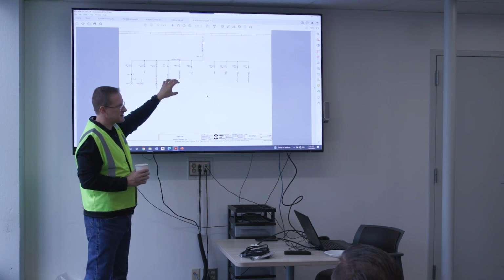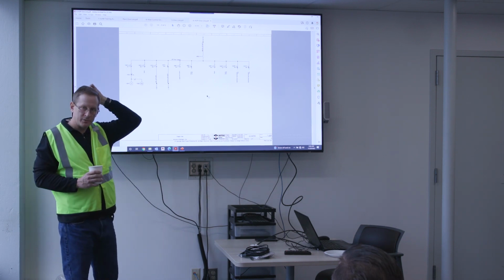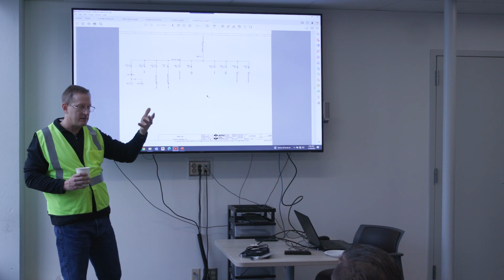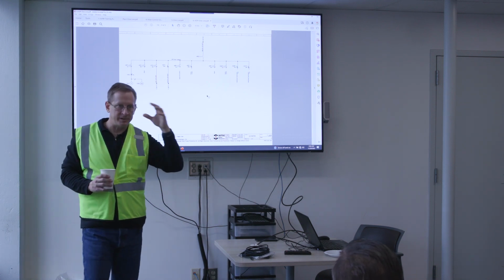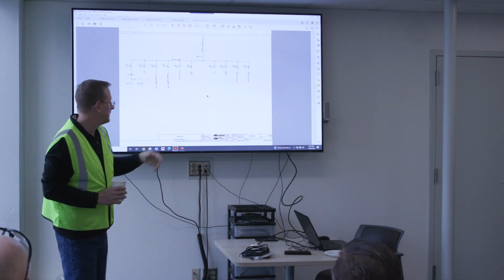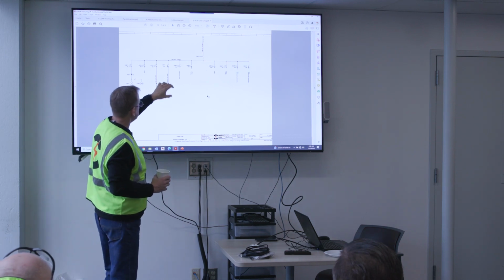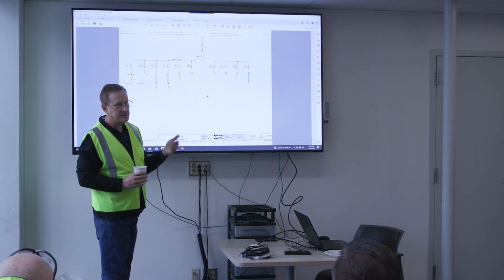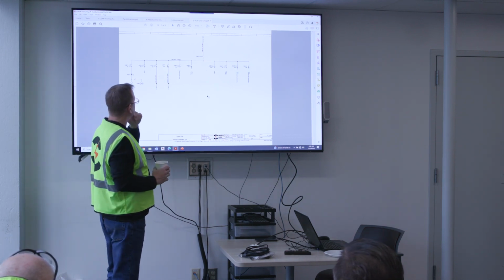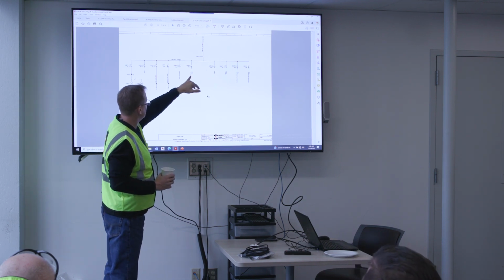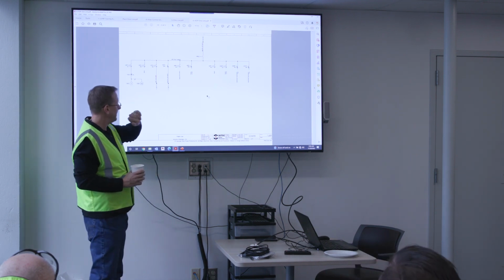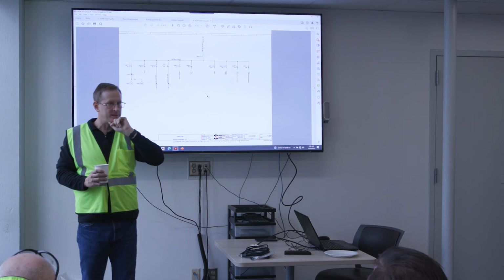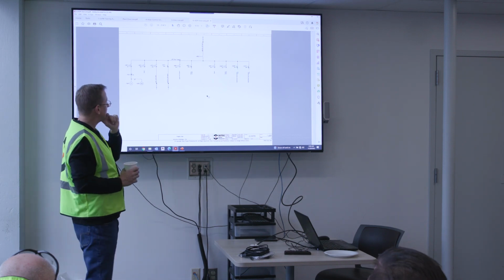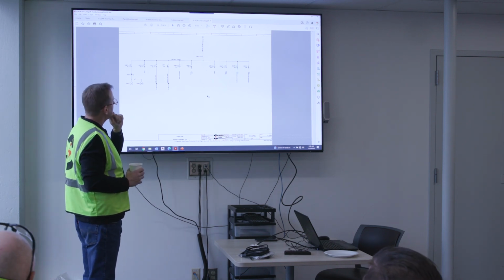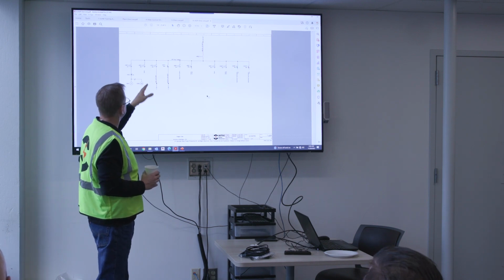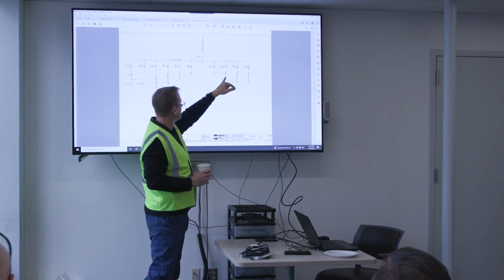There's actually another transformer that knocks it down to 120. So the fuel control panel on the day tank itself is a 120 panel. So there's a transformer in the ADP that knocks this down to 120 that goes into the fuel control panel. We've got a feed into our radiator. So our radiator is fed by a 480 volt three-phase out of the ADP for the radiator motor. And then we've got a couple spares. Also our DCP.